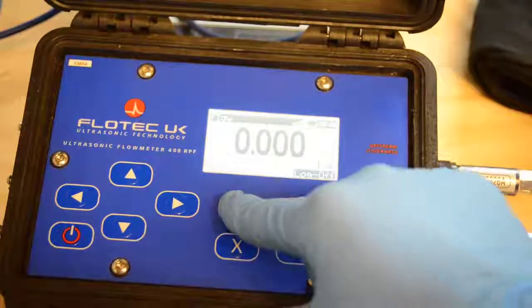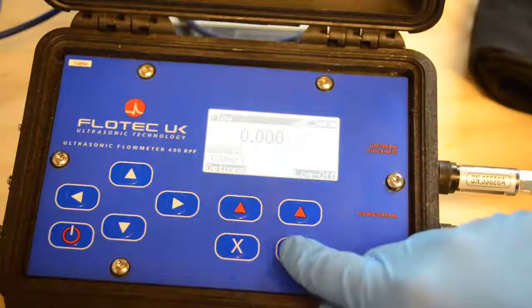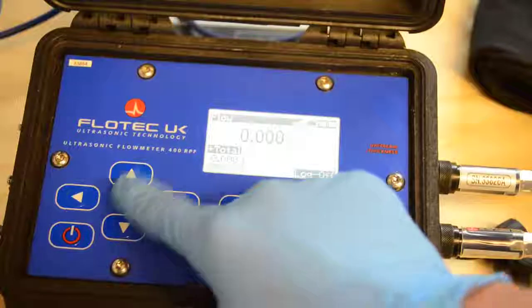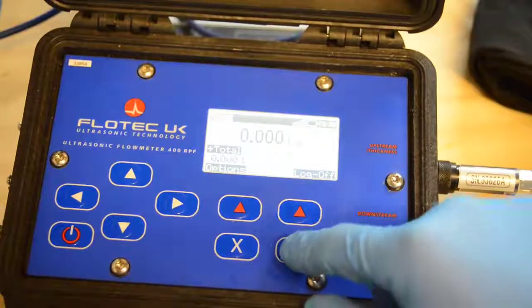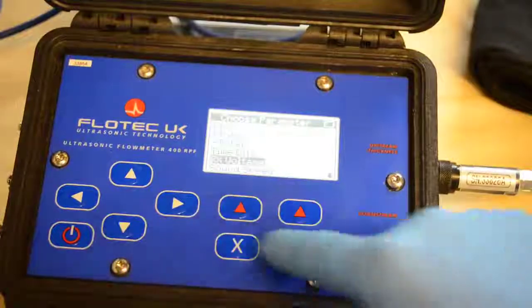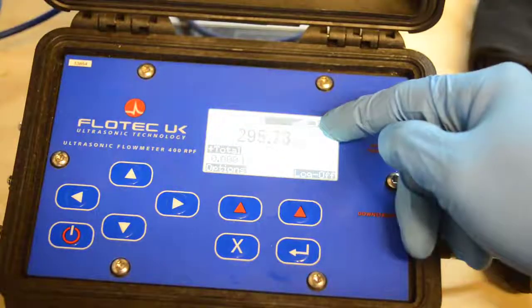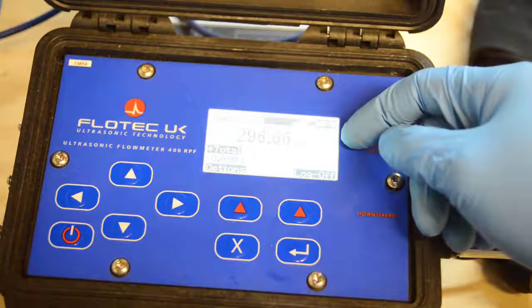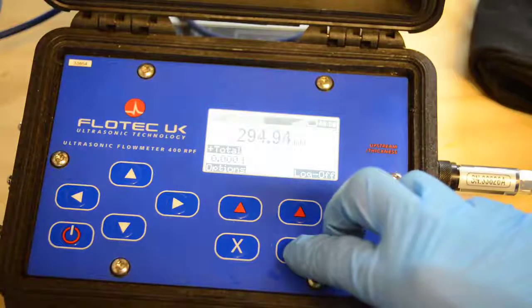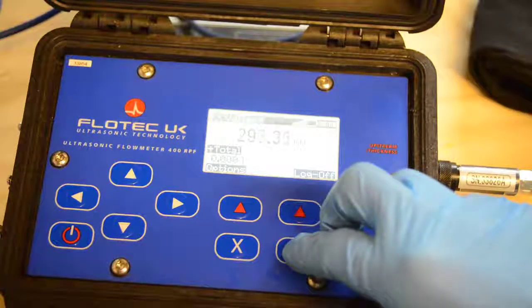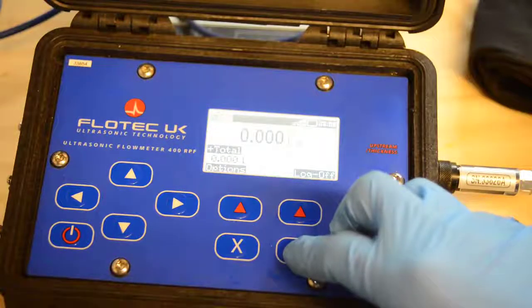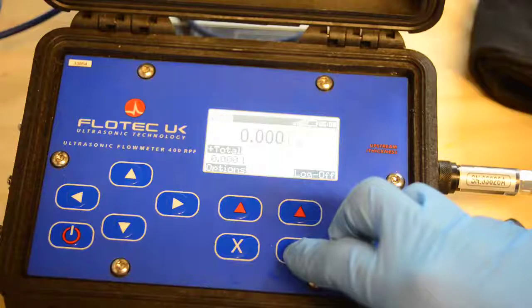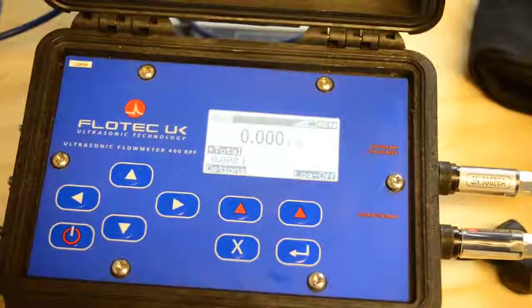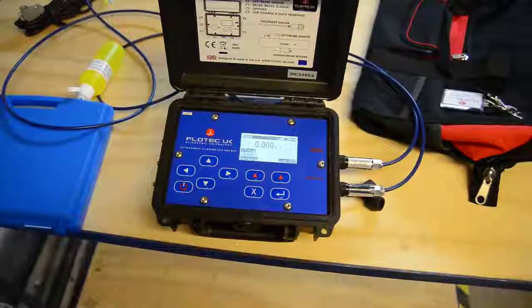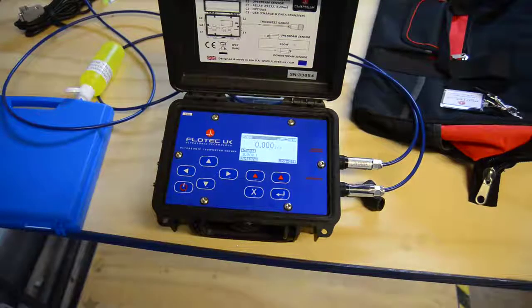We can also check, see if we can just confirm. If we choose as a measurement at the top there, let's just choose RX voltage. Okay, we have nearly 300 millivolts available. That's a big signal. The system can measure down to 1 millivolt, which is great. We transmit at high voltage and we can receive very small voltages. So we'll put that back to flow, and that is the setup in V mode of the device. We'll repeat this procedure for Z mode now.